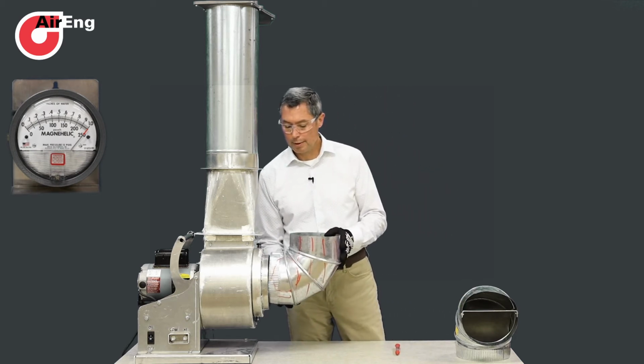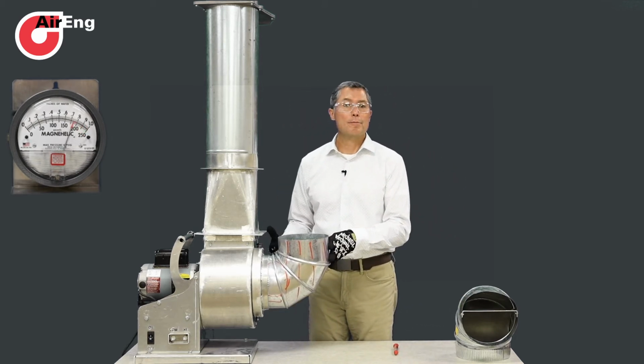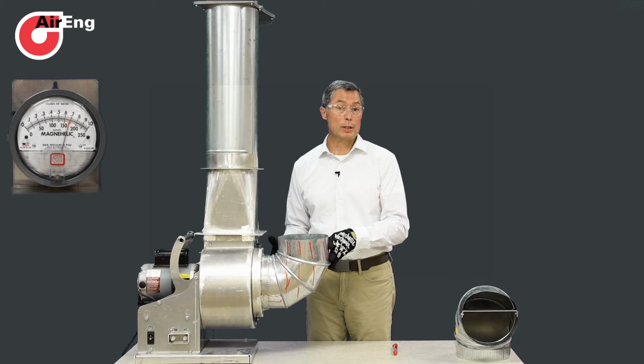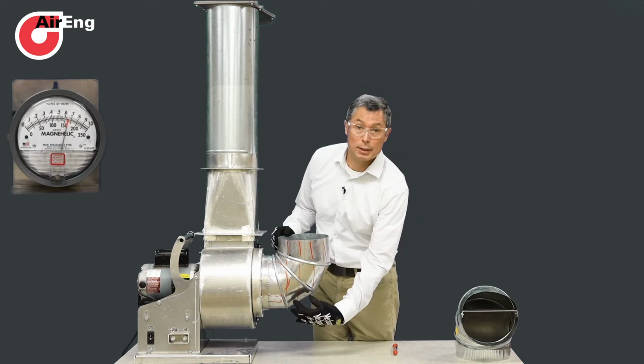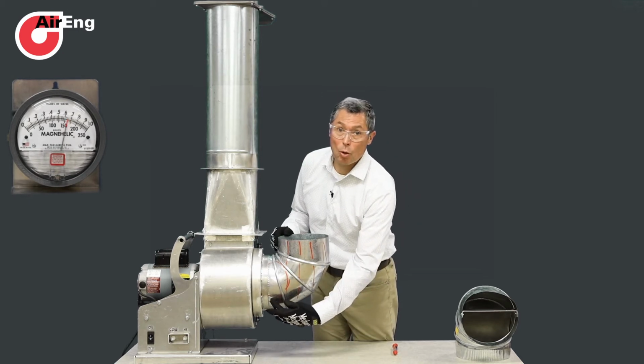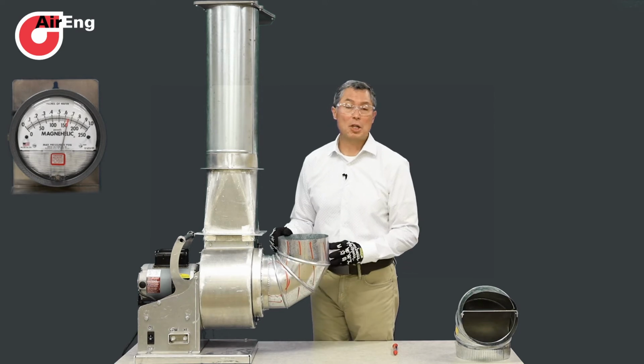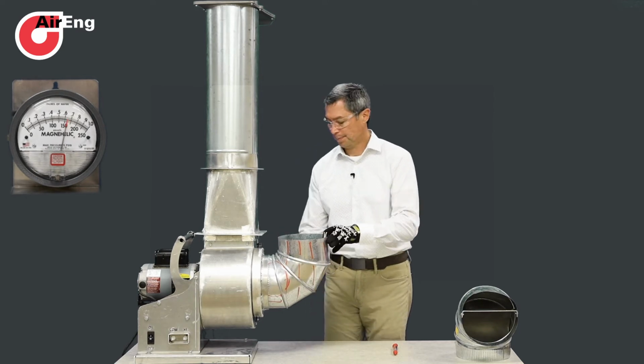So again, when we put it on the fan, performance goes down, sound increases. Air comes down, hits the bottom, bends 90 degrees over - the top portion of the wheel doesn't get any air, it's starved.